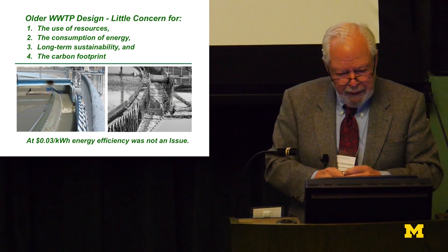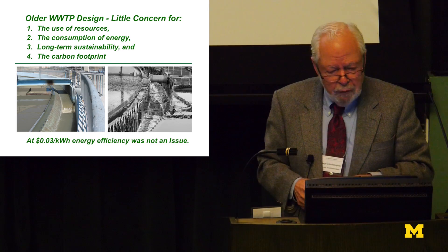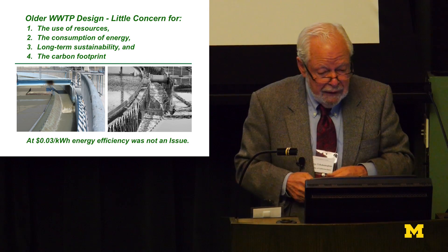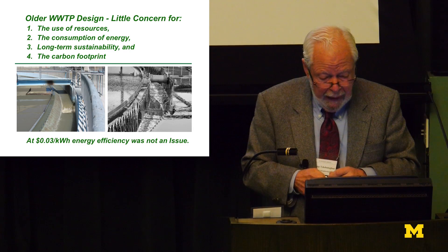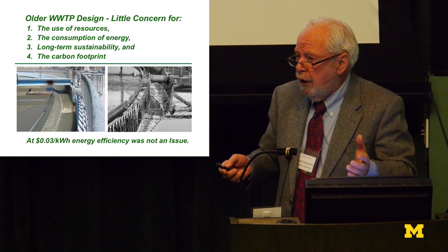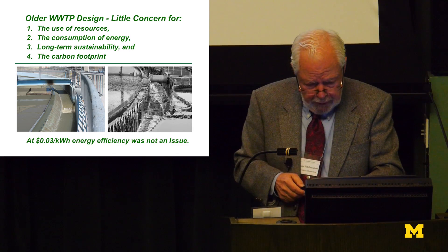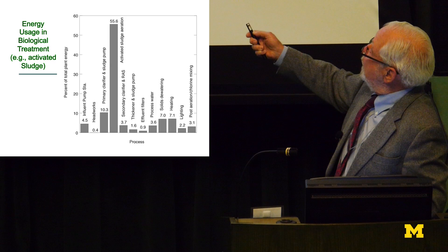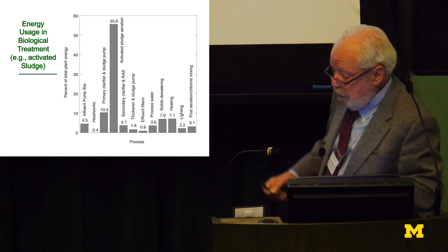With older treatment plants, there was very little concern for resource use, energy consumption, sustainability, or carbon footprint. We didn't even know those words existed. At three cents per kilowatt hour, it didn't matter much what you did. In biological treatment, if we look at energy consumption, clearly aeration is the giant in the room — 55% of the total amount used for wastewater treatment. These are issues that are going to affect our future designs.